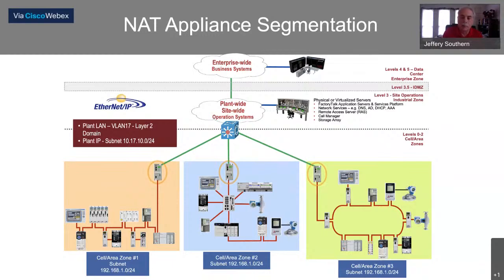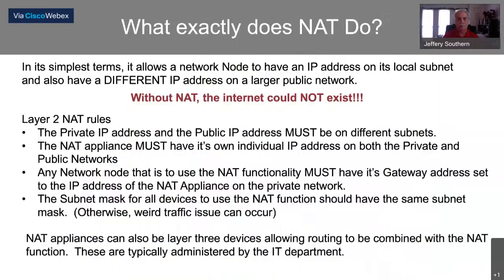It wouldn't be a physical possibility - you couldn't do it with Ethernet. So the NAT allows that to happen: it allows you to have a published IP address and a private IP address. Now the nice thing is I can maintain one program for these 3 processors, and I don't have to have 3 different programs with 3 different IP address schemes. Not too big a deal if you've got 3, but what if you've got a plant with 80 lines that are all identical? That could be a big problem right off the bat.